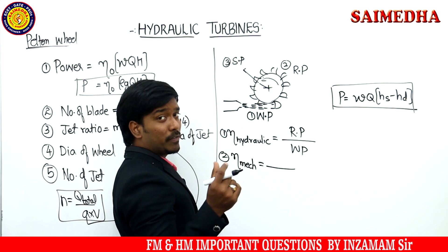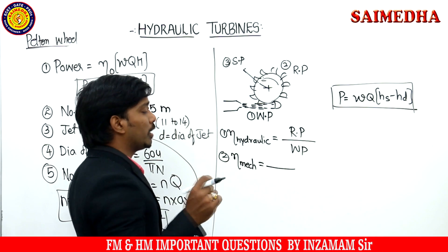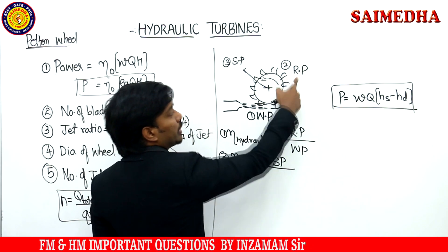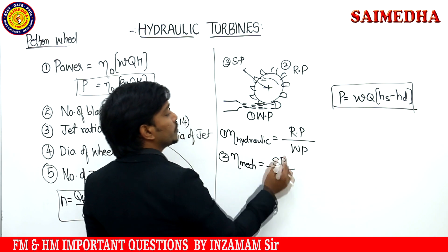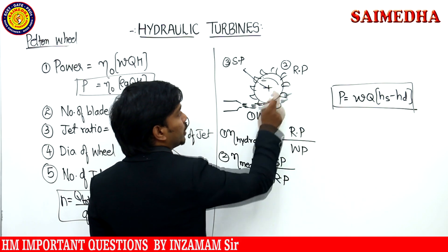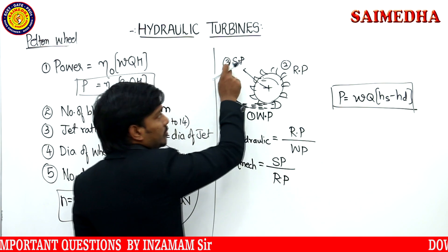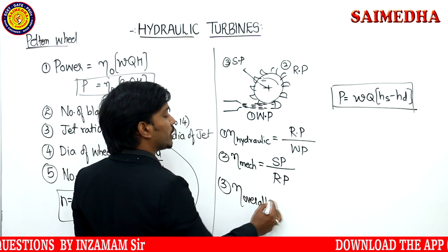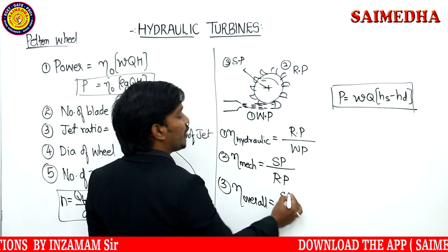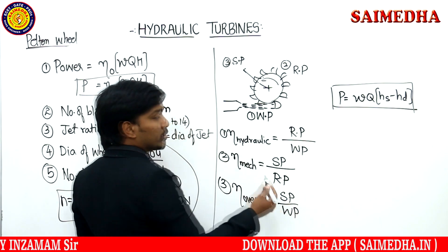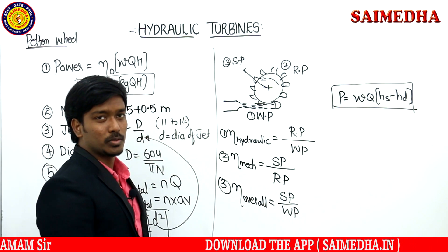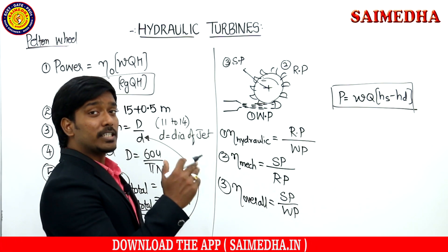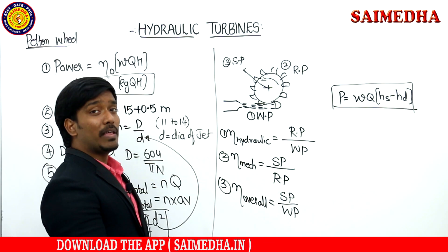The first efficiency is hydraulic efficiency: input is water power, output is runner power. The second efficiency is mechanical efficiency: input is runner power, output is shaft power — accounting for bearing loss and frictional loss. The logic is: output of stage 1 becomes input of stage 2. Overall efficiency is last divided by first, meaning shaft power divided by water power.